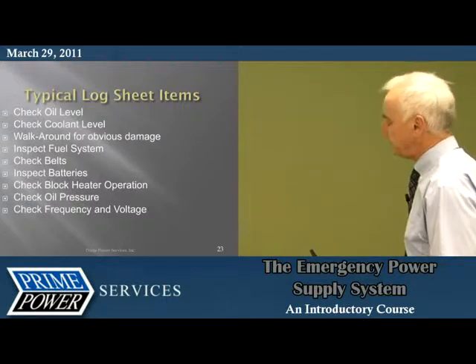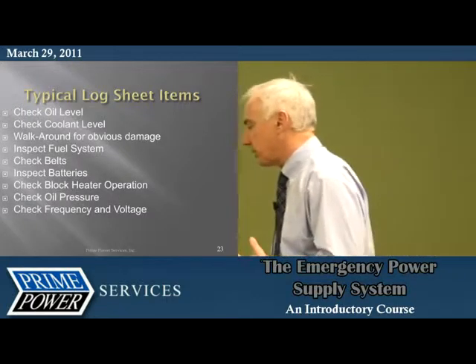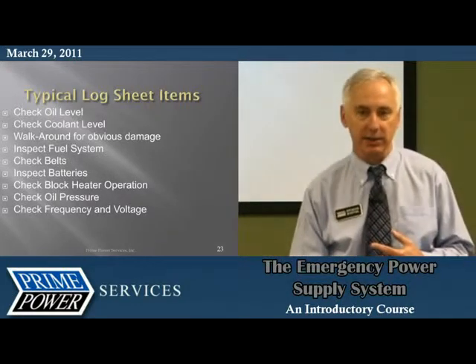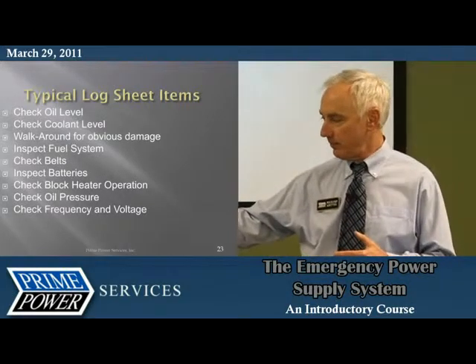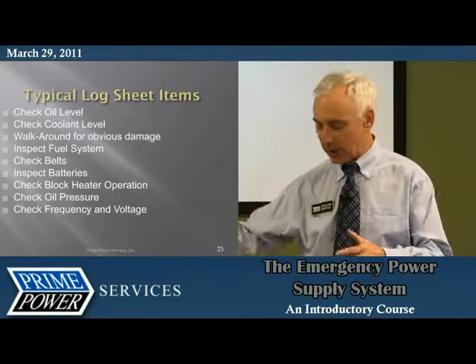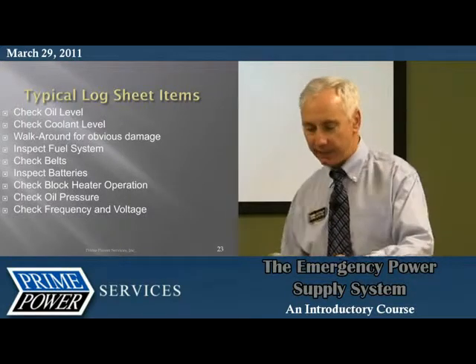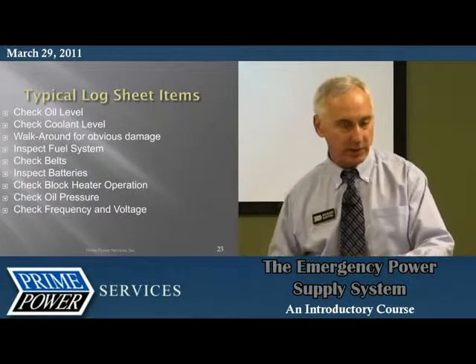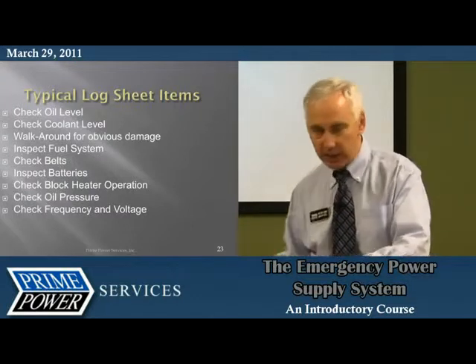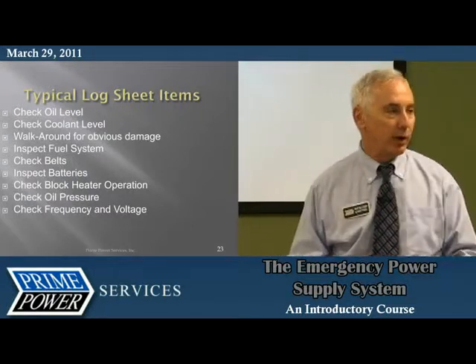Inspect the fuel system. What I'm talking about is the typical day tank, where we pump fuel from an underground storage tank into a smaller tank inside, for fire protection and storage reasons. That day tank typically has a test button on it. I want to know if it works.